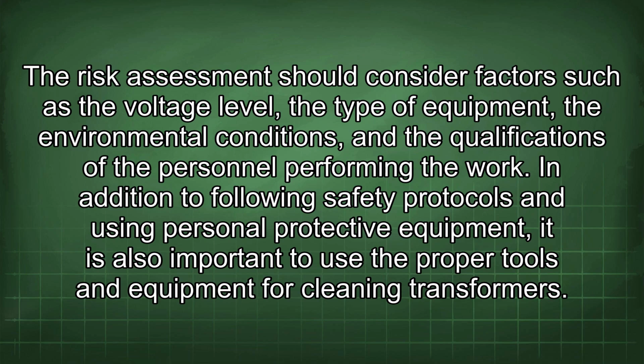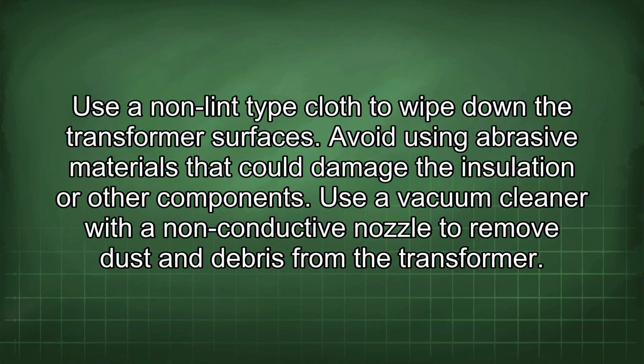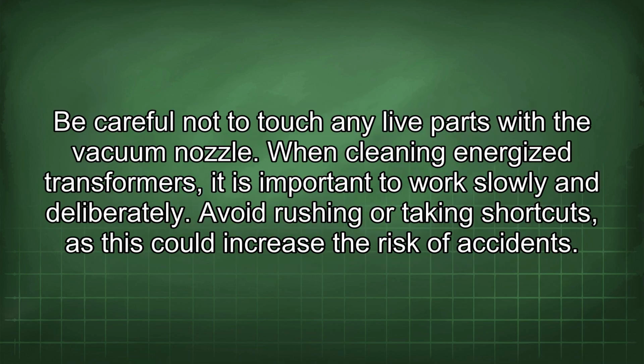In addition to following safety protocols and using personal protective equipment, it is also important to use the proper tools and equipment for cleaning transformers. Use a non-lint type cloth to wipe down the transformer surfaces. Avoid using abrasive materials that could damage the insulation or other components. Use a vacuum cleaner with a non-conductive nozzle to remove dust and debris from the transformer. Be careful not to touch any live parts with the vacuum nozzle. When cleaning energized transformers, it is important to work slowly and deliberately. Avoid rushing or taking shortcuts, as this could increase the risk of accidents.